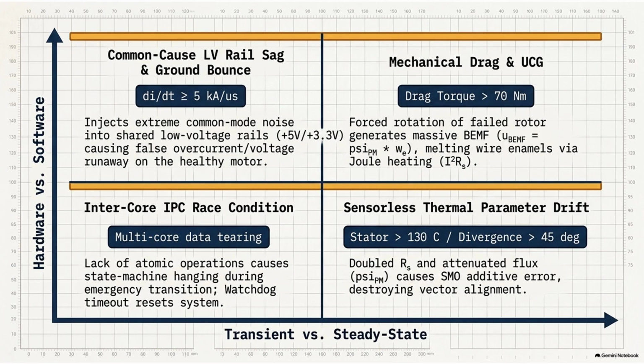Exactly. And because the Healthy Motors controller is attached to that exact same bouncing ground plane, its highly sensitive analog to digital converters, the channels reading the Healthy Motors speed and phase voltage and current, they suddenly see wild, impossible spikes in their data. Even though the motor is fine. Even though it's totally fine, the ground shifted, so the data shifts. I guess it's like turning on a massive industrial vacuum cleaner in an old house, causing all the lights to dim.